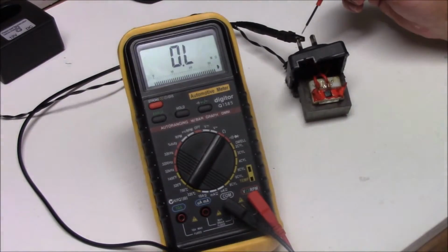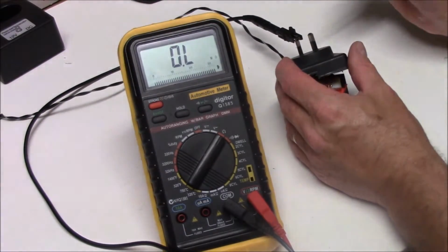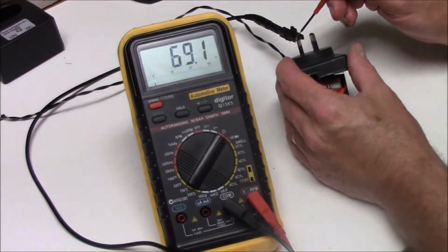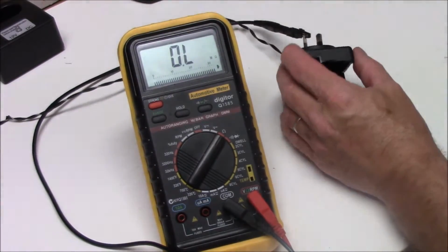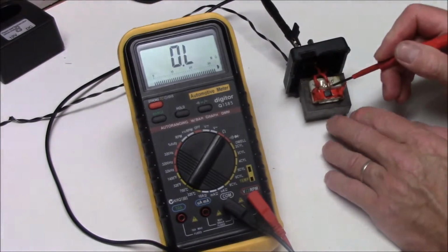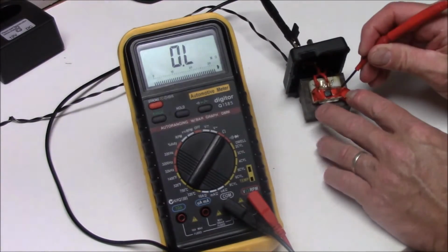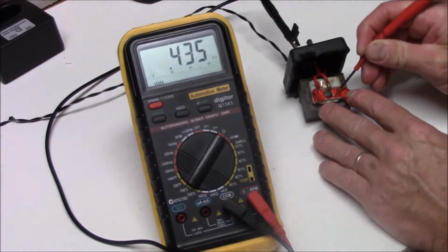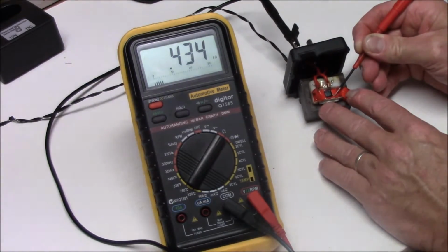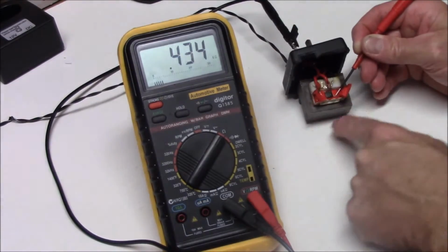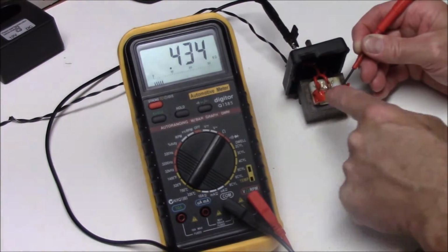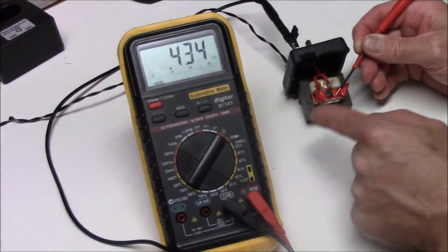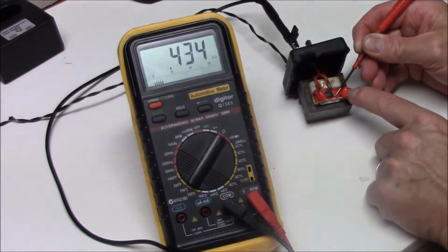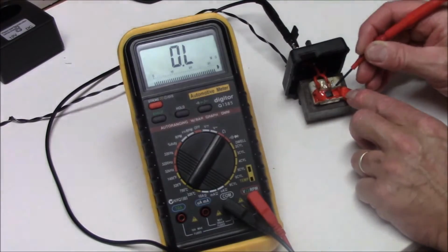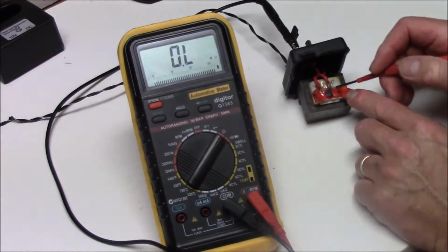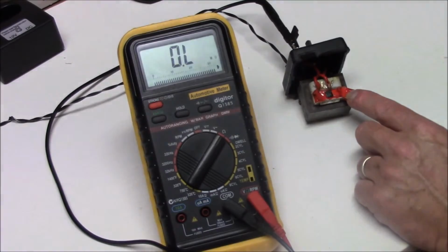So I've connected my negative terminal off my multimeter up here, and as you can see I've got good contact. Now if I bypass my thermal switch by going down to this point here, notice I've got continuity. That's a high continuity because it's going through the entire primary winding of the coil of the transformer, but that's okay - it's got continuity. That tells me the thermal switch is faulty. So all I have to do is replace that little thermal switch and the thing should be up and running again.